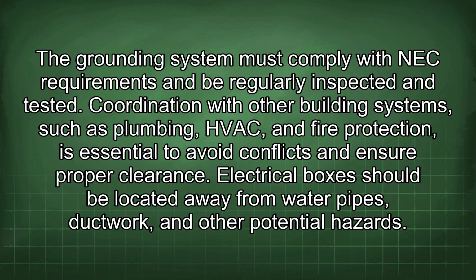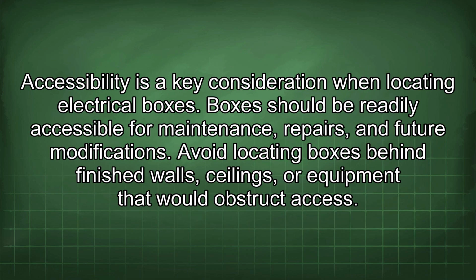Coordination with other building systems such as plumbing, HVAC, and fire protection is essential to avoid conflicts and ensure proper clearance. Electrical boxes should be located away from water pipes, ductwork, and other potential hazards. Accessibility is a key consideration when locating electrical boxes. Boxes should be readily accessible for maintenance, repairs, and future modifications. Avoid locating boxes behind finished walls, ceilings, or equipment that would obstruct access.